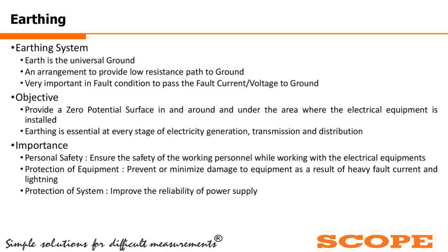Let's start with the earthing as decided. So earthing system, why earthing? Earth is a universal ground. It is considered a thumb rule for every measurement or design of any system, electrical or even electronic. There should be an arrangement to provide a low resistance path to the ground. That is the main purpose of having an earthing. It is the most important part when a fault appears. If the system is healthy, earth is not playing that big a role. But when there is any fault in the system, it becomes the most crucial thing, because it gives the condition to pass the fault current or fault voltage to the ground.